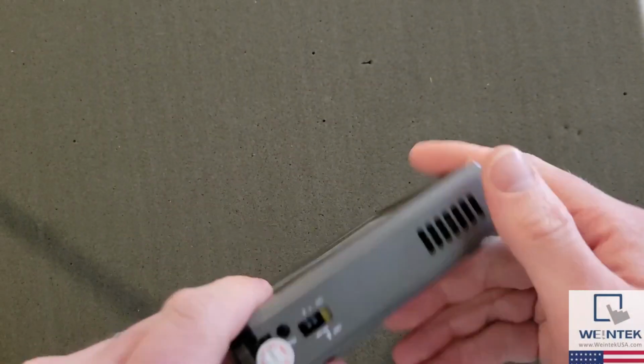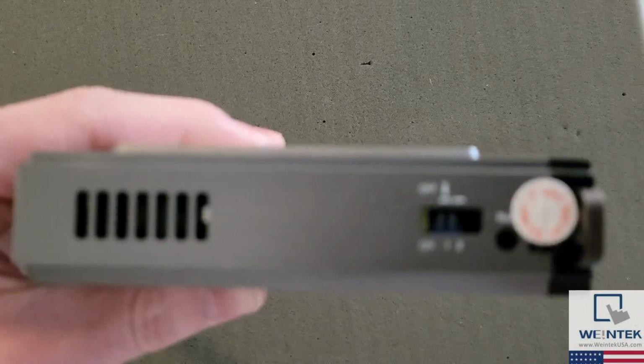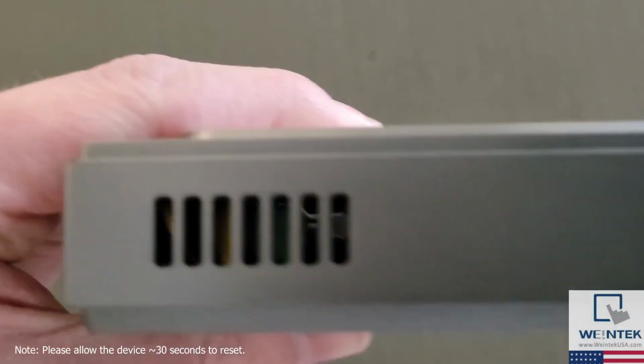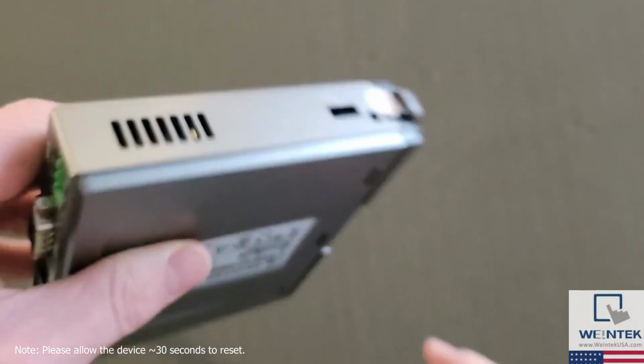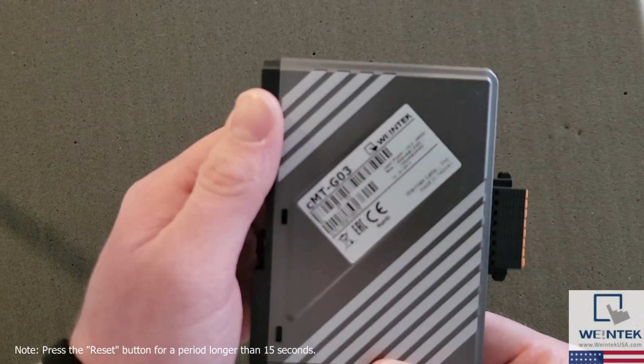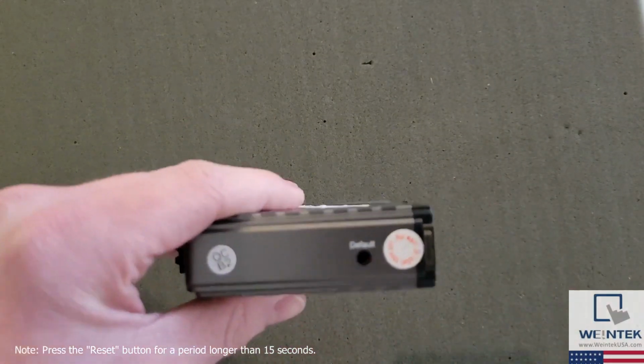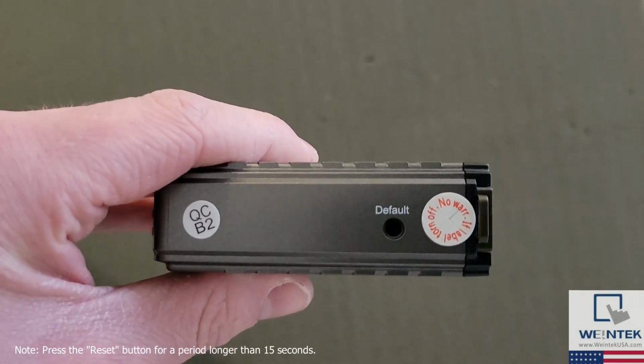As a general rule, you can factory reset screenless HMIs by powering on the device while dip switch 1 and 2 are set to the on position. Our Gateway series has a reset button that will reset the unit if it is pressed for at least 15 seconds.